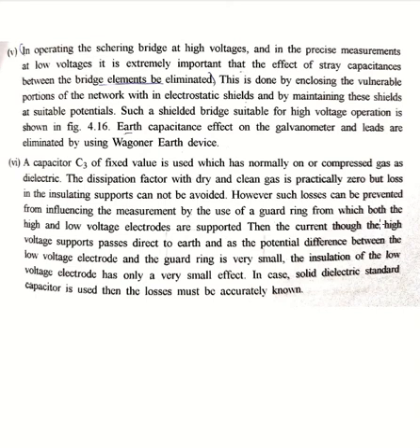So the current through the high voltage supports passes directly to the earth, and as the potential difference between the low voltage electrode and the guard ring will be small, the insulation of the low voltage electrode has only a very small effect. In case a solid dielectric standard capacitor is used, then the losses must be accurately known for the capacitor.